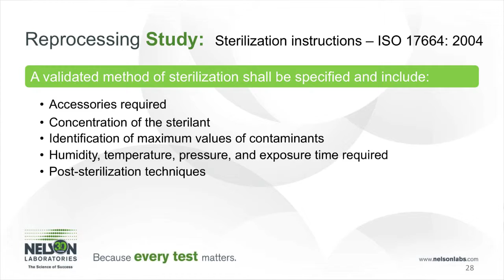The steps for sterilization validation include sterility assurance level validation with half-cycle parameters. Then we perform a dry time validation to ensure that the devices are fully dry. And then we perform temperature profiling on the devices as well to ensure that they get up to the correct temperature during the exposure phase.